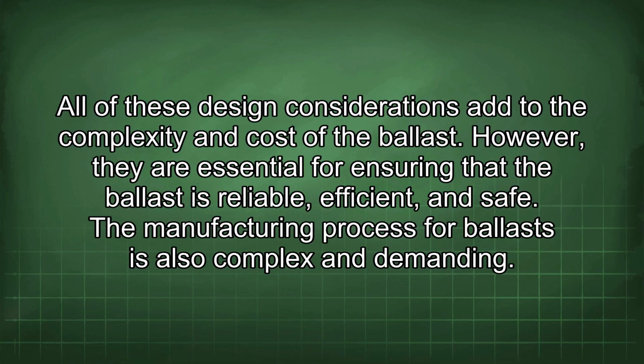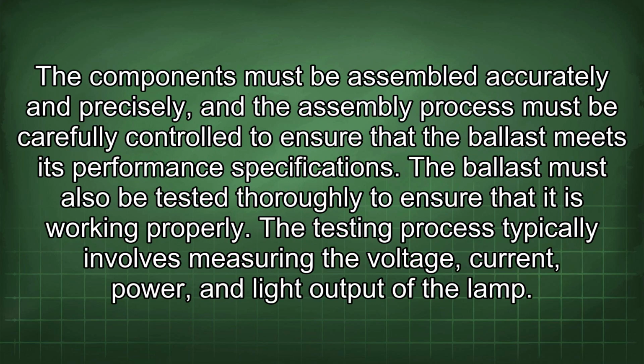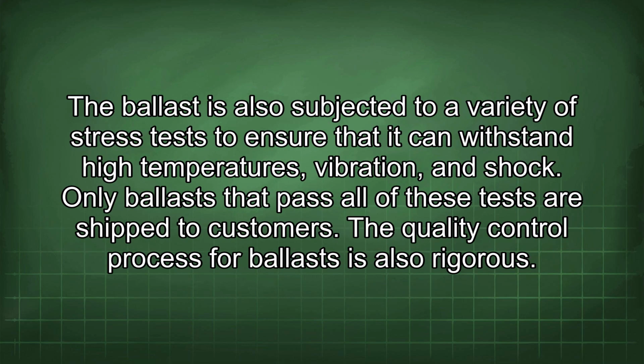The manufacturing process for ballast is also complex and demanding. The components must be assembled accurately and precisely, and the assembly process must be carefully controlled to ensure that the ballast meets its performance specifications. The ballast must also be tested thoroughly to ensure that it is working properly. The testing process typically involves measuring the voltage, current, power, and light output of the lamp. The ballast is also subjected to a variety of stress tests to ensure that it can withstand high temperatures, vibration, and shock. Only ballasts that pass all of these tests are shipped to customers.